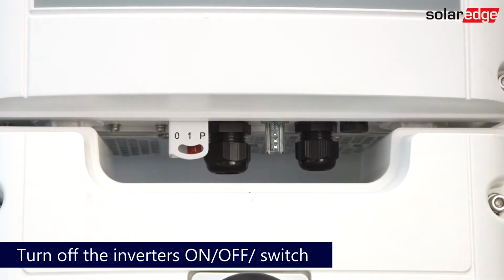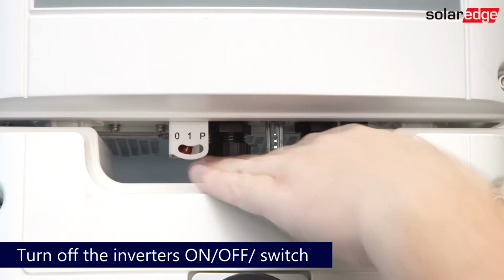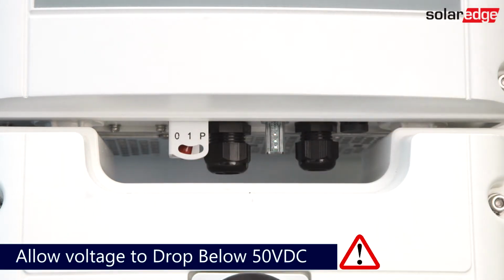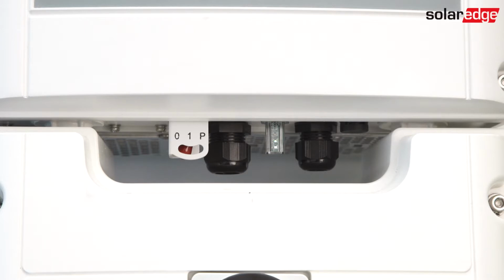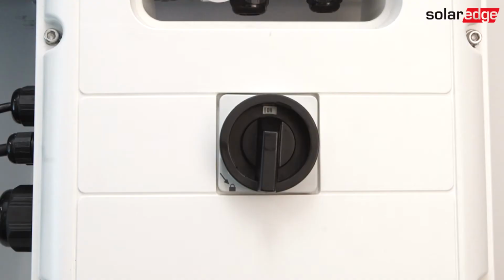Before we begin, ensure the system is de-energized. Turn the inverter on-off P-switch to the off position. Allow the inverter to reach safe DC voltage, indicated by the red LED light going away on the LED tube, or the voltage falling below 50 volts DC. Next, turn off the DC safety switch and remove the cover of the connection unit.